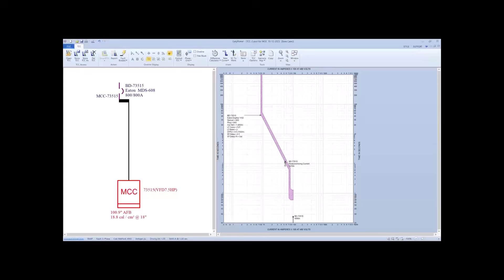Insert arcing current. In some cases, when I'm working on relay coordination, the breaker is okay, but the arcing current is seen by the breaker only in long time. So with this function, we plot it, and we can also move the TCC of the breaker in order to improve the arc flash, right?